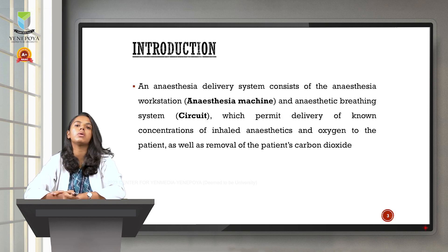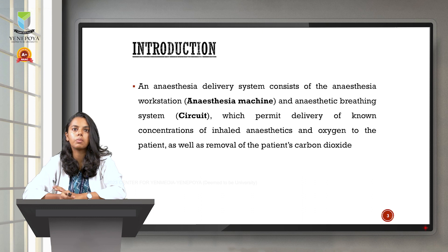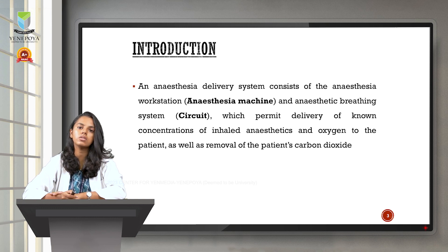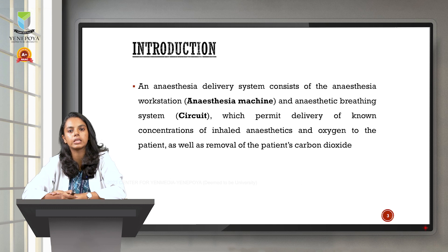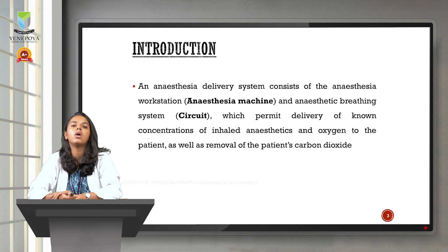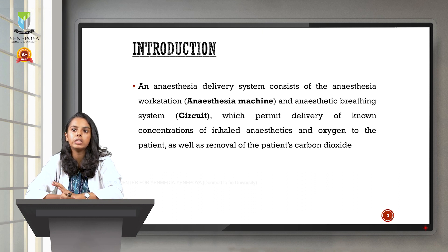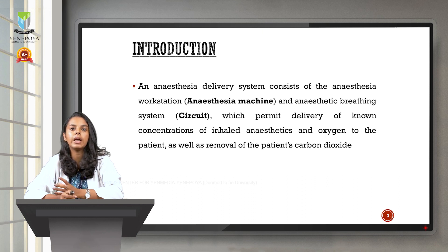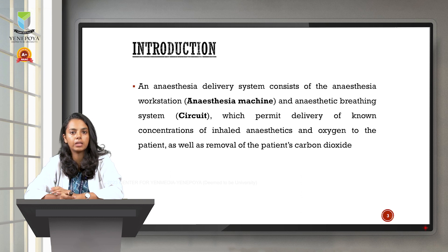The anesthesia delivery system mainly consists of the anesthesia machine as well as the breathing circuit. Combining the anesthesia machine and the breathing circuit gives us the anesthesia delivery system. Anesthesia is not just one particular gas — it's a mixture of gases that we give to the patient in order to facilitate a surgical procedure. The main function of the anesthesia machine is to deliver a known concentration of anesthetic mixture of gases to the patient, as well as to remove the carbon dioxide exhaled by the patient.